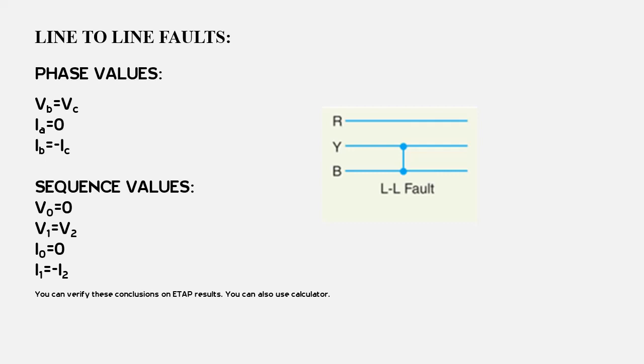Now, if we discuss line to line faults, take the same example with three phases: phase A, phase B, and phase C. If the fault is occurring on phase B and phase C, then the voltages on phase B and phase C will be equal, and the current flowing through the fault path will be equal in magnitude and opposite in phase. For example, if one angle +θ is flowing through phase B, then one angle −θ will be flowing through phase C.